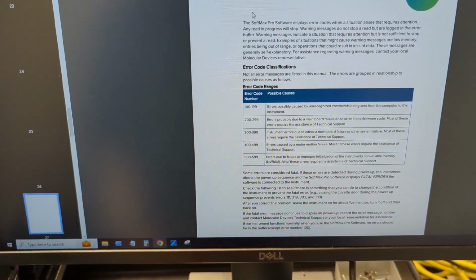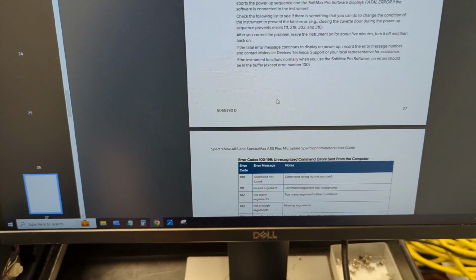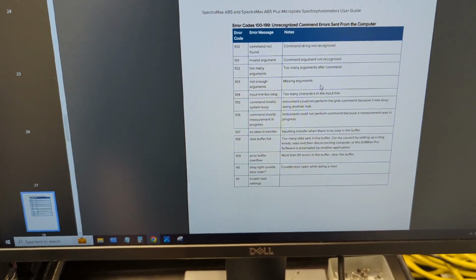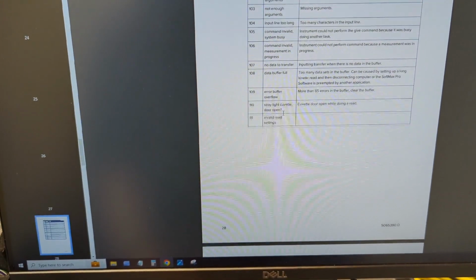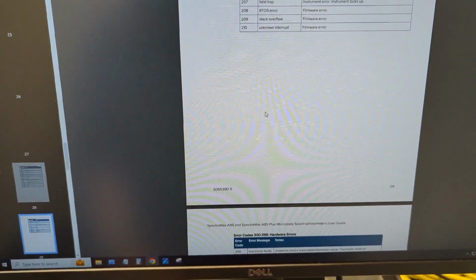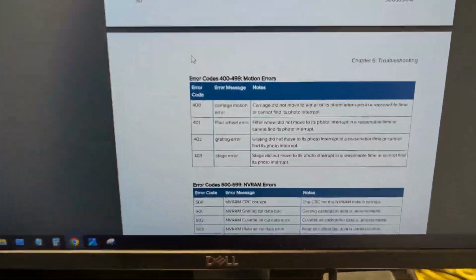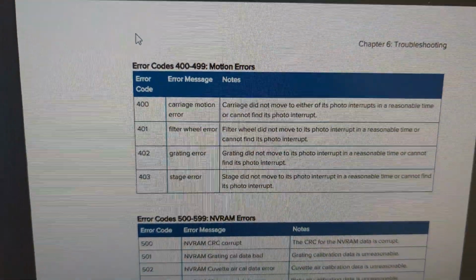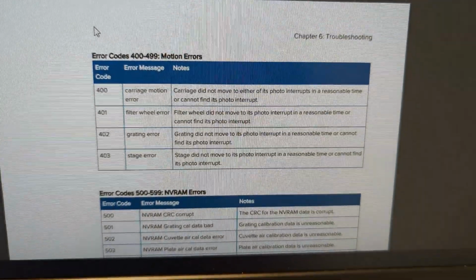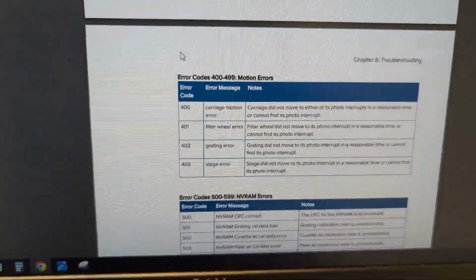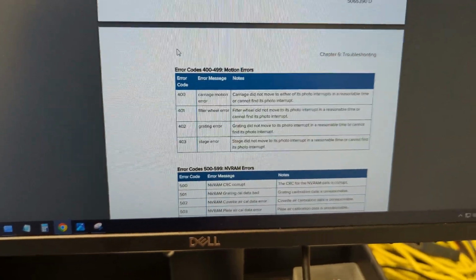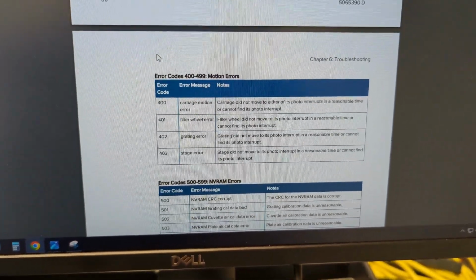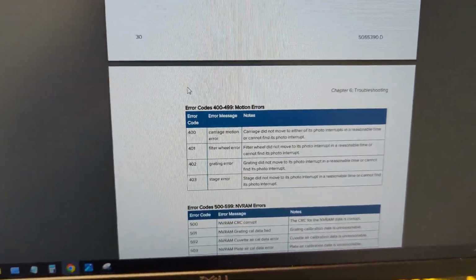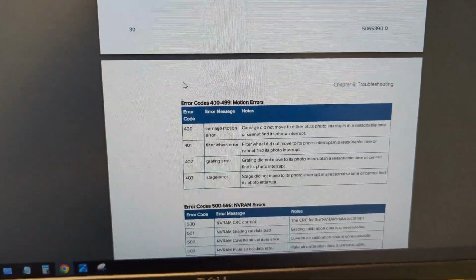And then this troubleshooting area is just telling you what the error codes are. That is it. They don't give you any real troubleshooting. There are no troubleshooting trees or anything like that. But let me show you what this filter wheel error is. So here it is. Filter wheel did not move to its photo interrupt in a reasonable time, or cannot find its photo interrupt. Now, when this company says photo interrupt, they are referring to an optical homing sensor.